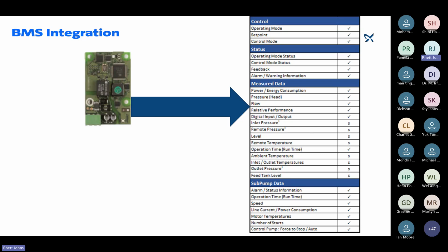So we can see whether we make a change within the system, such as running those pumps a little bit more slowly or dropping our pressure set point. We can make those sorts of changes and monitor what impact that has on the energy consumption of the system. So in a typical pump controller, like we've got on the left, the communication card would pass through the set points that you see on the right. And you, as a factory owner and potentially an energy engineer, can start making informed decisions and logging the data off of your pump systems.